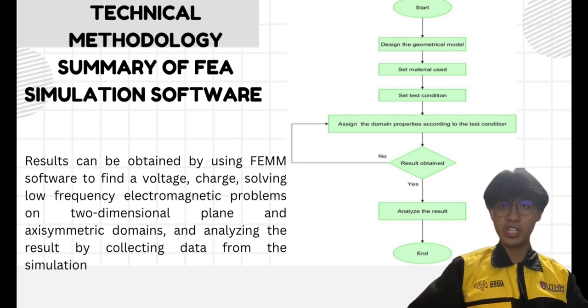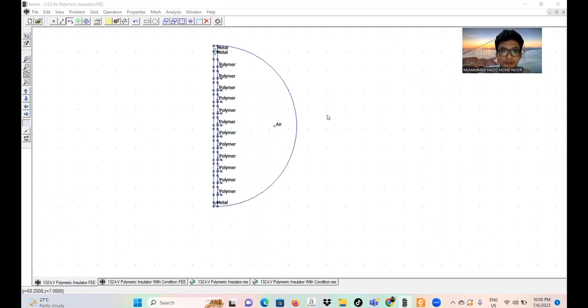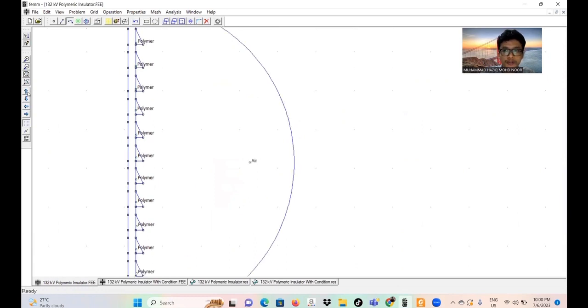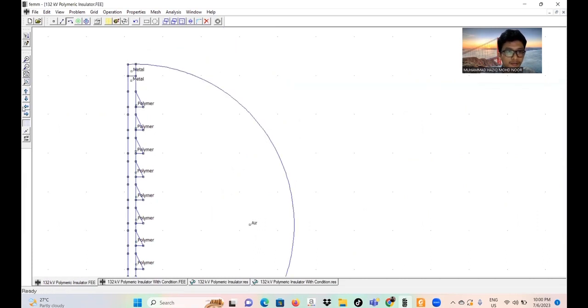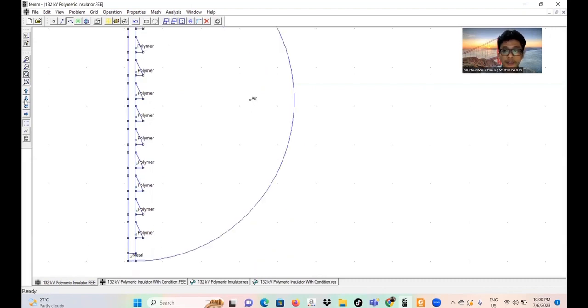Assalamualaikum. So today I would like to demonstrate the electrical stress performance on an alternate shed polymeric insulator for a 132 kV system by using finite element analysis. The finite element analysis that we would like to perform is by using FEMM software. Based on what is demonstrated here, this is the 12 alternate shed, three-phase polymeric insulator that carries a 132 kV system.